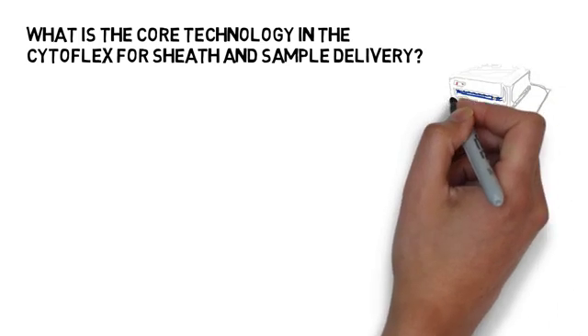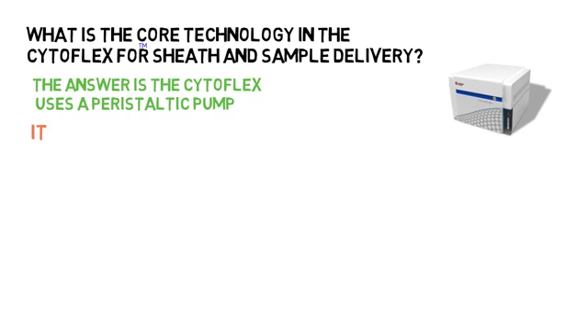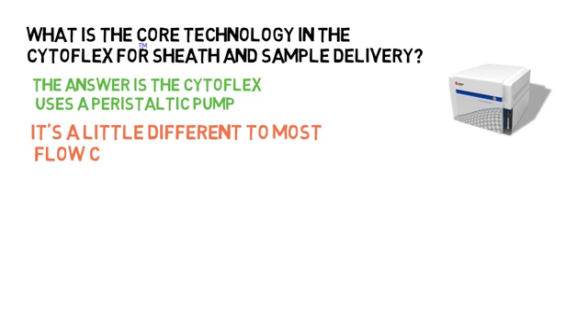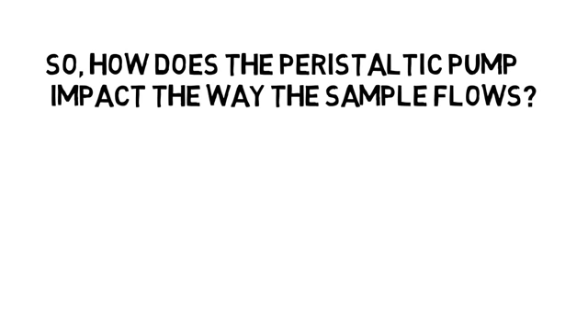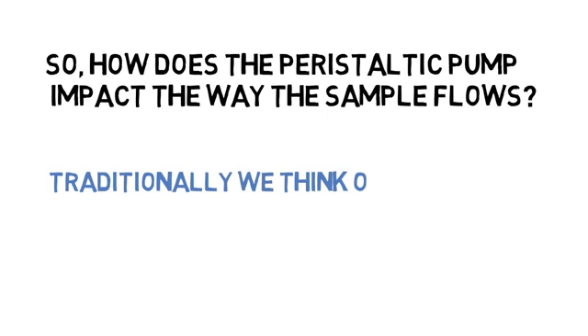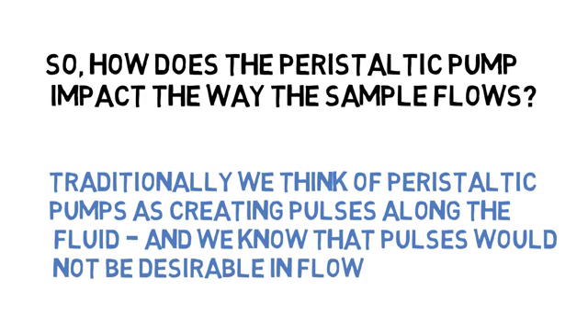So what is the core technology in the Cytoflex? The Cytoflex uses a peristaltic pump that is quite different from many other cytometers. It is important for us to look carefully at this technology to see how it works and how it impacts the quality of the data produced. Traditionally, we think of peristaltic pumps as creating pulses along the fluid, and we know that pulses would not be desirable in flow cytometry.